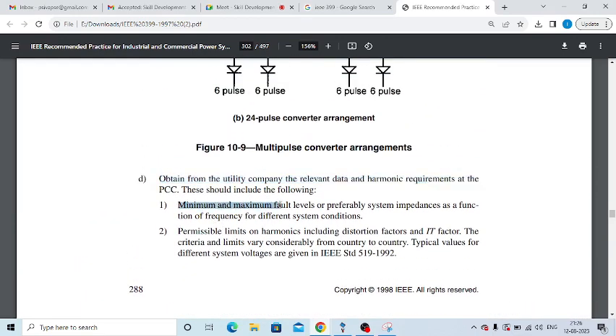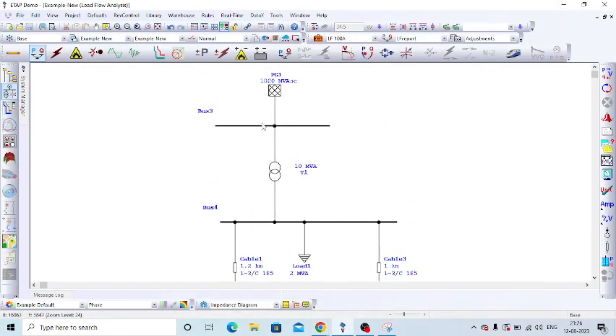Then, as I told you, this is the short circuit of the grid. We have to get it, and the background harmonic voltage, and then how much distortion we have to maintain at this particular location. Normally we have to comply with the harmonics limit at PCC. PCC means point of common coupling. That is the interface point between the utility company and the industrial company. The interconnection point is called PCC. Generally, this PCC point is the billing point where the utility or discom or transmission company charges the particular industrial company for the energy consumption. So for that location, we have to maintain it.